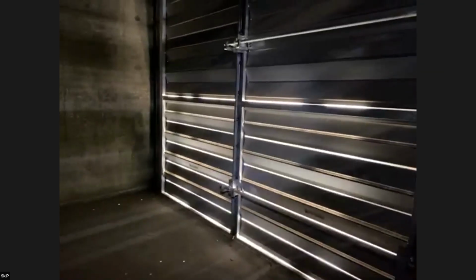What happens is if those were open 100% and we were bringing in 100% air, this other set of dampers on the right would be closed, and all the return air, instead of flowing back through, would then get pushed out the exhaust side that we walked through in the very beginning. It's a little harder to show on the film, but that's kind of the premise behind the outside air economizers and what they're there for.